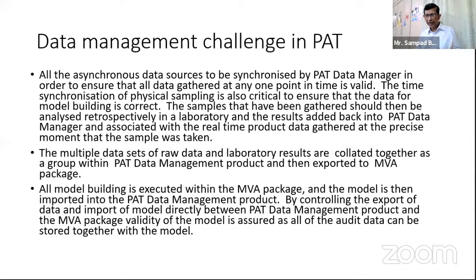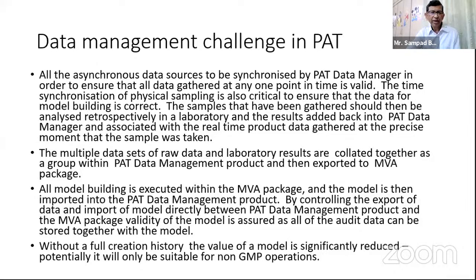Otherwise you land into a problem. I have some experience where somebody went simply for a Bruker variety of NIR, and then found that the MVA package they thought suitable does not sense data from the Bruker model directly - they had to go through an additional interface to make it compatible. So compatibility between your sensing equipment, your MVA, and your data management product has to be established first of all, and of course all of this requires full traceability.